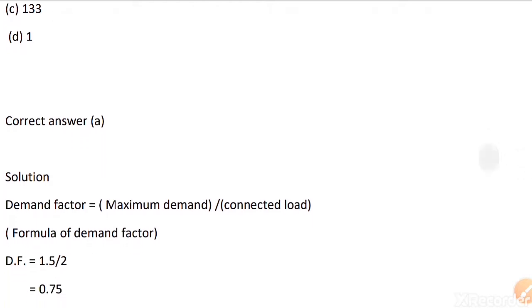So demand factor is maximum demand by connected load, 1.5 divided by 2 is equal to 0.75.